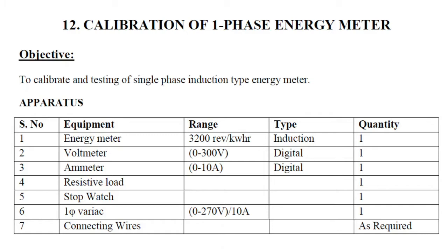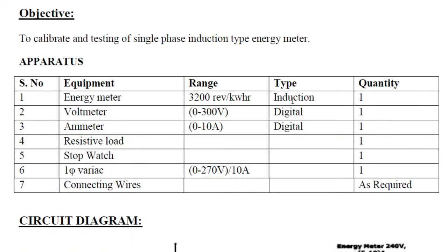Let us see what apparatus is required to perform single-phase energy meter calibration. We need an energy meter of induction type with a range of 3200 revolutions per kilowatt hour — this is the meter constant. We also need a voltmeter of 0 to 300 volts range and an ammeter of 10 amps range, both of digital type.